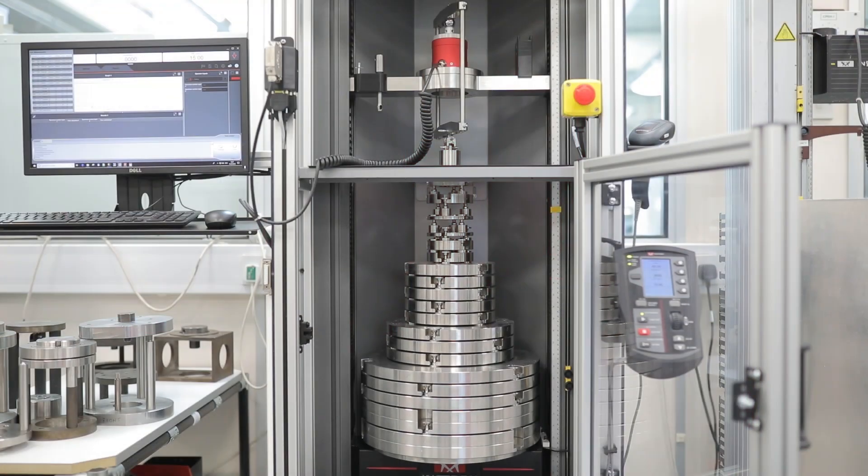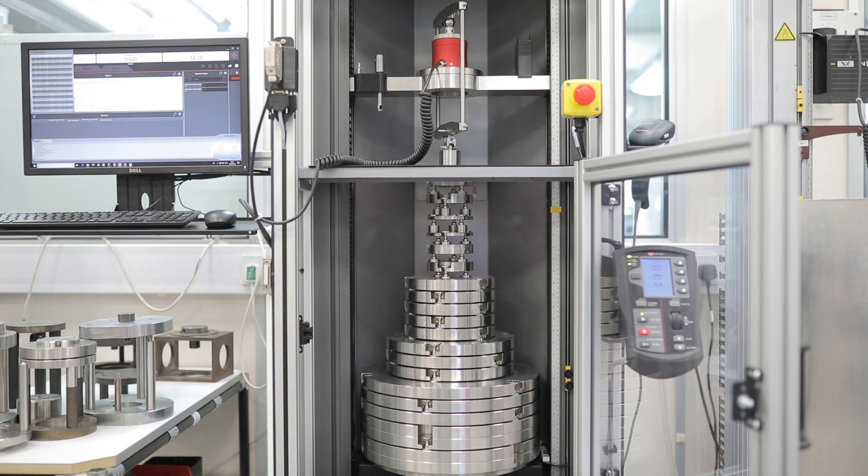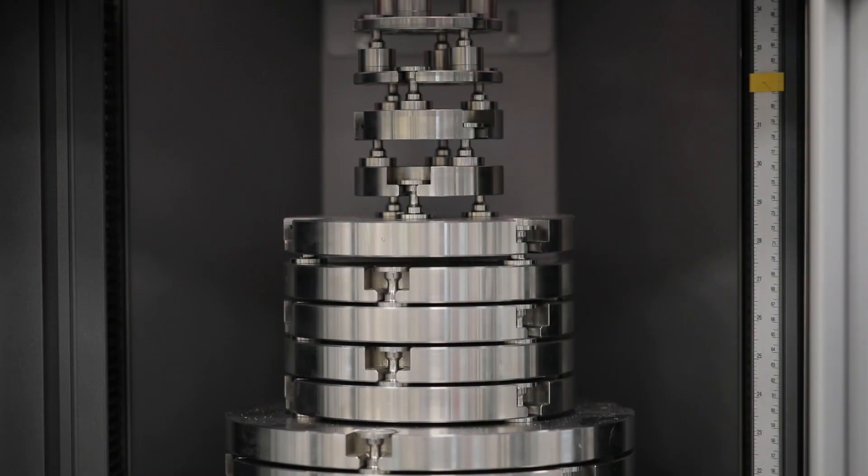But before any load cells are ready to ship, they are put through a final step of calibration using traceable reference devices.